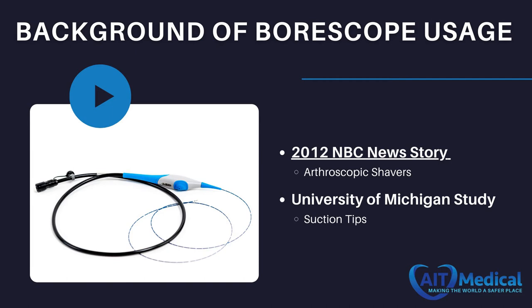Upon inspection of the facility's shavers with a borescope, the shavers were found to have bone and tissue in the internal channels. In 2011, Jahan Azizi, a risk management clinical engineer at the University of Michigan Health System, examined 350 surgery-ready suction tips that had been cleaned according to the manufacturer's instructions. Upon inspection with a borescope, all 350 suction tips contained blood, bone, tissue, or rust. After taking those 350 suction tips back through the cleaning process according to the manufacturer's IFU, all but seven still contained debris.